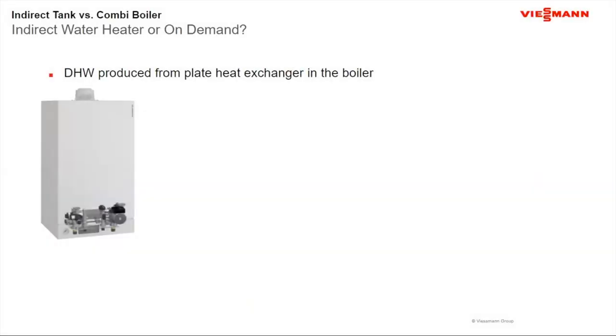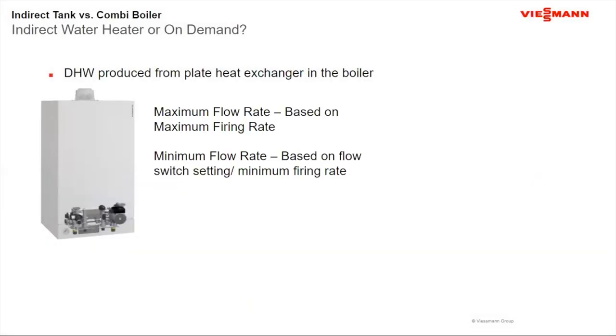Okay, so with a combi boiler, domestic hot water is produced from a plate heat exchanger. Talked a little about this earlier. If I look at my maximum flow rate, the maximum flow rate is based on the firing input. So if the input's 150,000 BTUs, I'm generally at about 3.4 to maybe 3.7, depending on the temperature rise. If the input's around 199,000, I can get up to 4 gallons per minute at about a 90 degree rise. So that is really what I am going to get out of it.